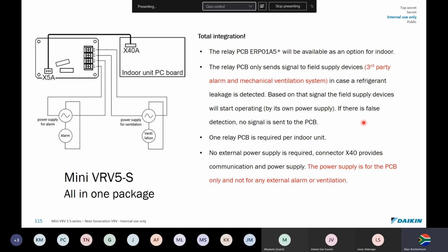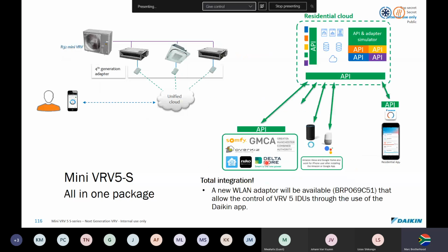Why? Because the X40 connector provides communication and power. And I've put here in red that the power supply is for the PC board only and not for any ventilation. So this would be like a normally closed, normally open, or a volt-free contact that this would send out. So this doesn't put out voltage. The outdoor unit will do, but not this. The electricity it gets is purely to drive its own electronics.